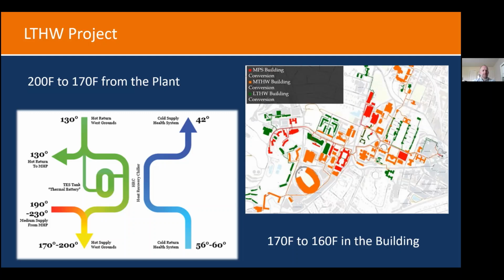Instead of rejecting heat to cooling towers, we recover it. We add a second compressor to the heat recovery chiller to make an even hotter discharge, so we can take the return water from the buildings across grounds and heat it using the same piece of equipment that's making chilled water. This gives an efficiency approaching 5 to 6, so for every 1 unit of energy in, you get about 6 units of energy out.